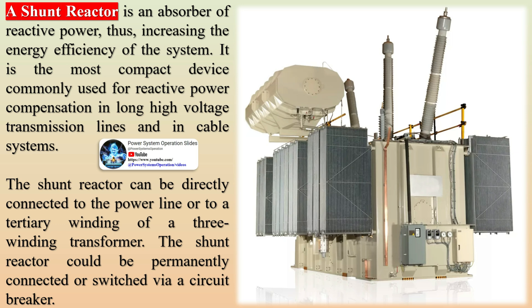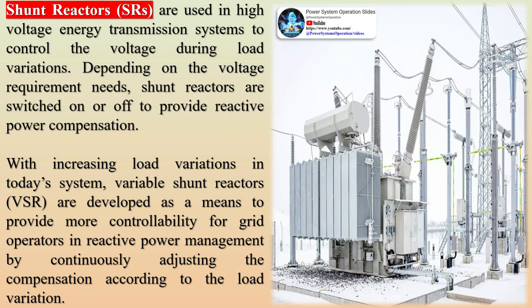The shunt reactor could be permanently connected or switched via a circuit breaker. Shunt reactors are used in high-voltage energy transmission systems to control the voltage during load variations. Depending on the voltage requirement needs, shunt reactors are switched on or off to provide reactive power compensation.